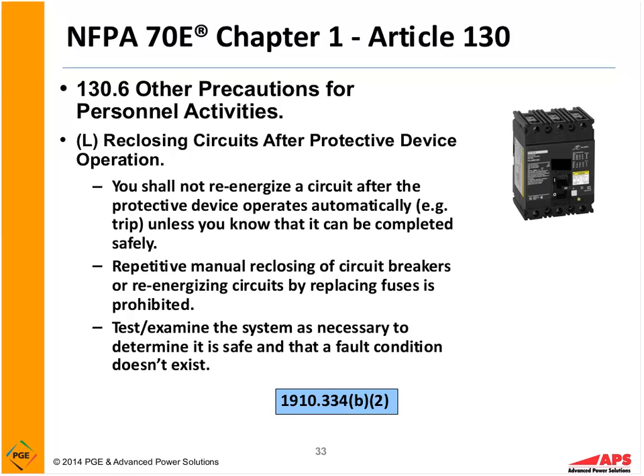But let's say downstream we had a phase-to-phase or phase-to-ground fault, so we actually had a direct fault condition. You close that breaker, put fuses in, and reclose back into that fault. The breaker can actually explode on you, okay?